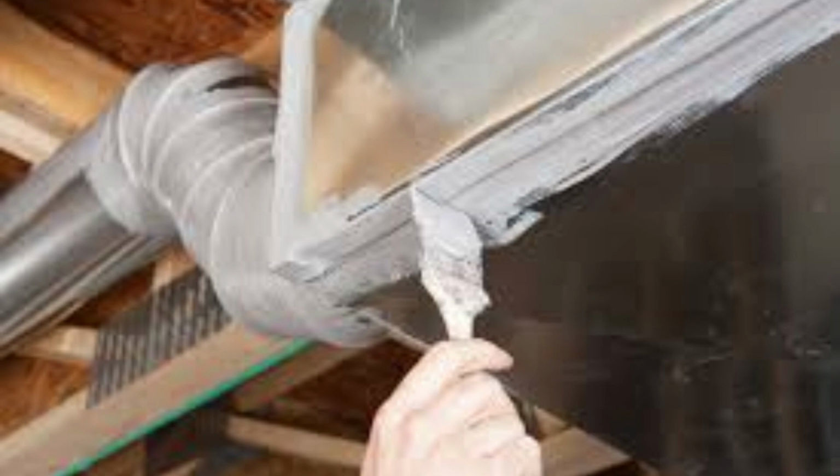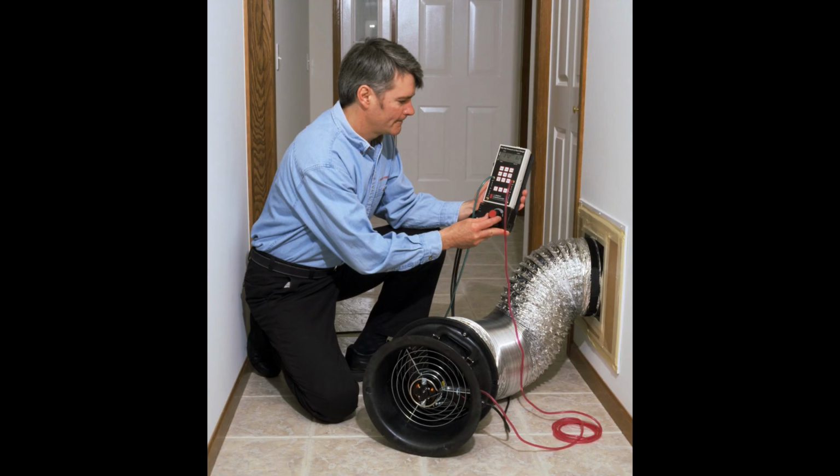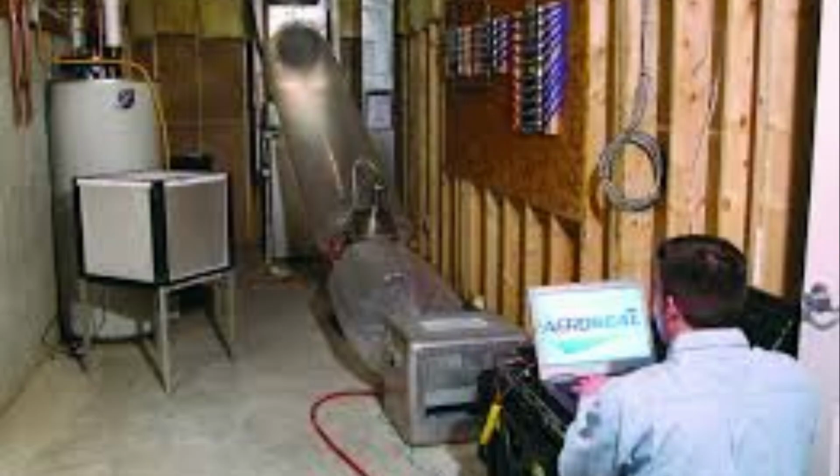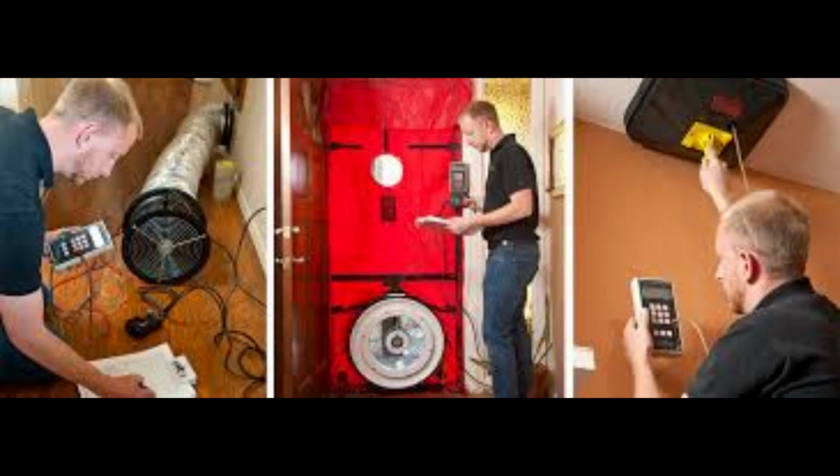Number 6. Air duct sealing and leak testing. Sealing ducts effectively is vital for preventing air leaks and ensuring efficient airflow throughout the system. Leak testing identifies areas of potential air loss, allowing for targeted improvements. Correct sealing reduces energy waste and lowers utility bills, contributing to overall system efficiency. The choice of sealants, whether mastic, tape, or gasketing, should be based on joint configuration and surface conditions. Adhering to ASHRAE 90.1-2019 requirements can further enhance the effectiveness of duct sealing, ensuring a well-functioning HVAC system.